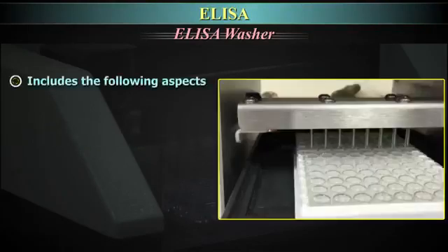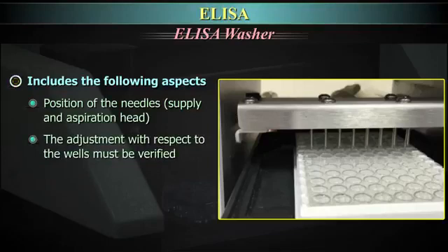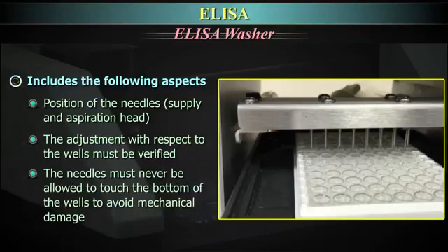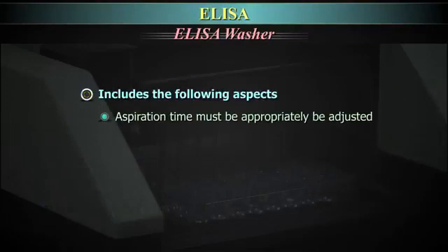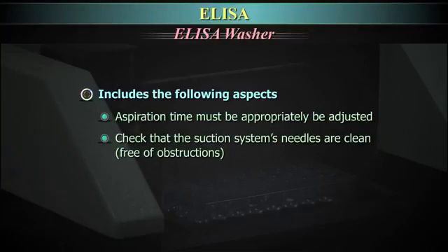It includes the following aspects. Position of the needles, supply and aspiration head. The adjustment with respect to the wells must be verified. The needles must never be allowed to touch the bottom of the wells to avoid mechanical damage. Aspiration time must be appropriately adjusted. Also, check that the suction system's needles are clean, that is free of obstructions.